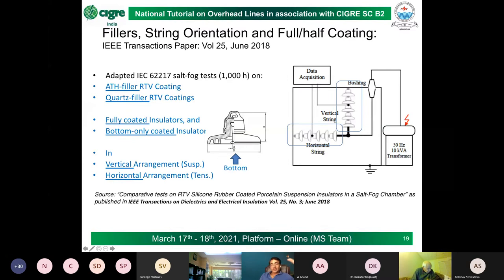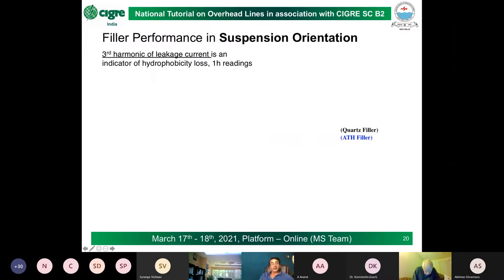I will not go into too much detail here, but the idea of this is a paper which was by Dr. Edward Cherney, who has played a lead role in RTV coating, and is called by many, including Terna, the father of modern RTV coating. Dr. Cherney assisted me with this work, and he worked largely with a gentleman from Istanbul University. What we did here was look at different fillers, the ATH filler, the quartz fillers, fully coated insulators, bottom-only coated insulators, and saw how they perform in the 1,000-hour tests when vertically aligned, like a suspension insulator, and then horizontally aligned. So that's essentially what this test is.